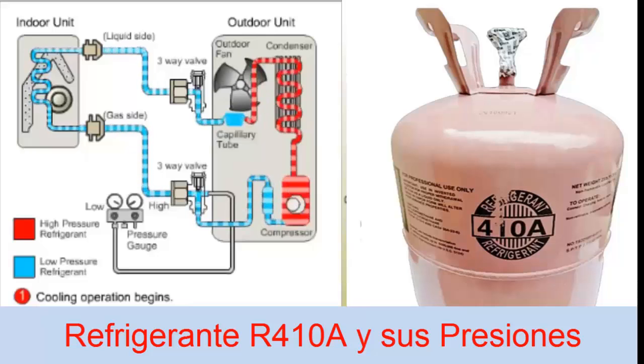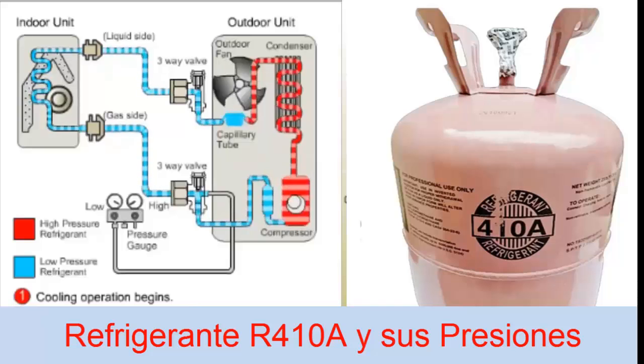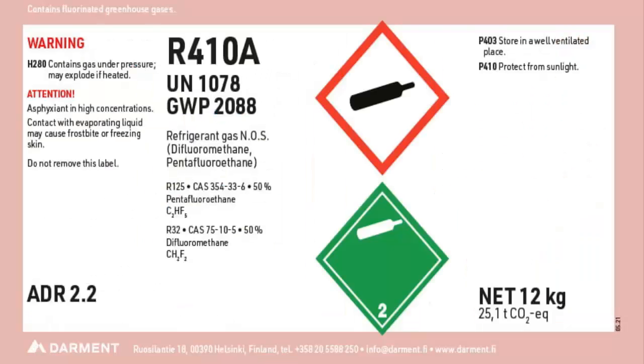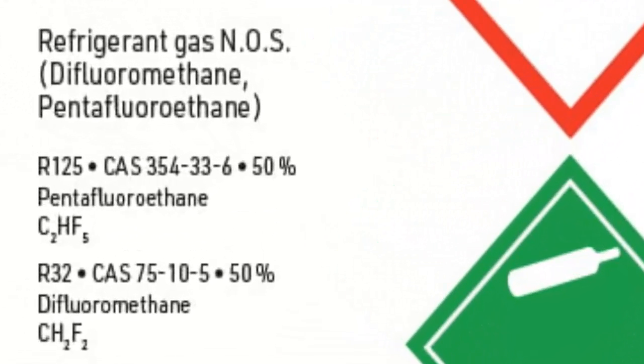These are the main work pressures of our R410A. As for the gas and its properties, we can say that it is a gas formed by the mixture of two gases — it is not a single-component gas but a two-component gas. It is formed with R125 at 50% plus R32 at 50%. Two components form the R410A.